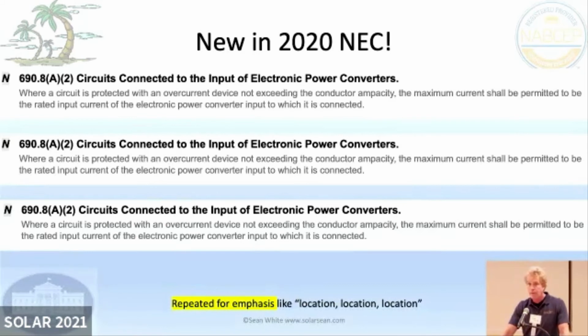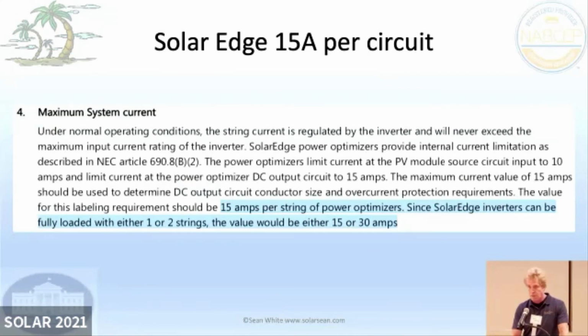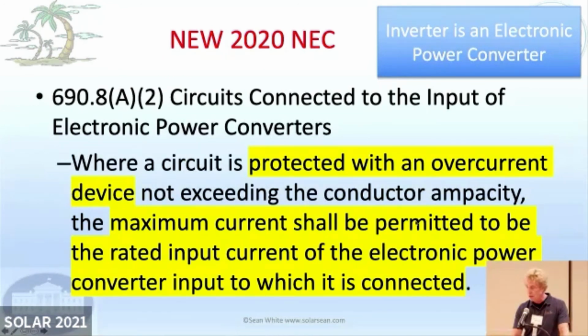Now we could do that with PV inverters. There's just a different way of sizing the wire for the input of a PV inverter, and it's based on the maximum amount of current the PV inverter can take, as long as you have an overcurrent protection device there too. That's another thing that's a little bit different. It's a different way of doing it instead of basing it on the PV. With DC to DC converters, just like with the voltage, it's going to be based on what the instructions say. So just say, for instance, SolarEdge, you want to read their instructions because they can have new stuff coming out and different ways of doing things, but 15 amps per circuit. And so this was the new thing that I just told you about. So we just talked about that. We can base the current on the input of the inverter instead of the output of the PV. That's kind of a big deal.